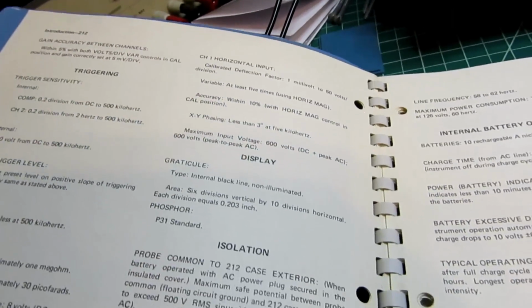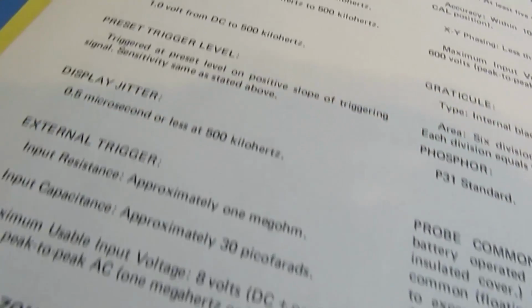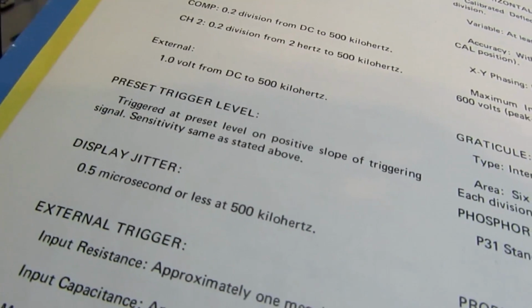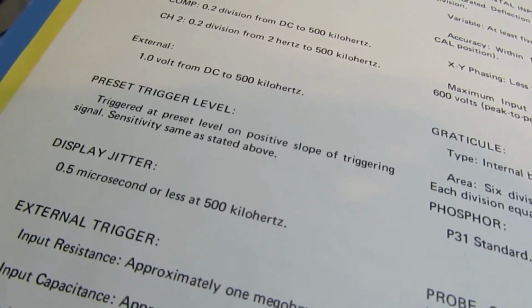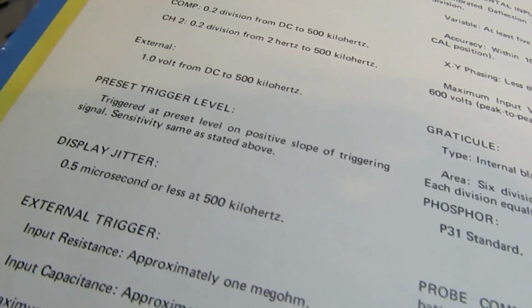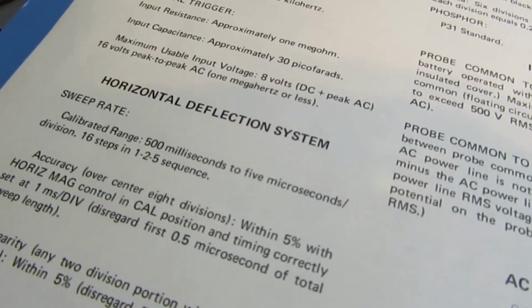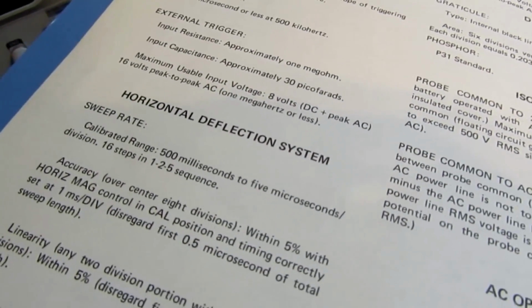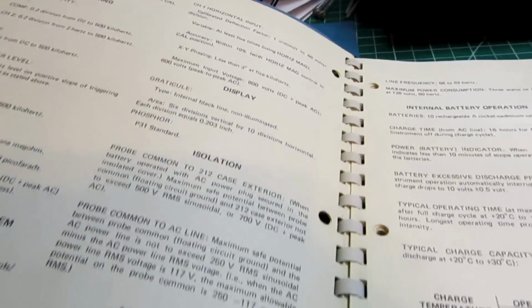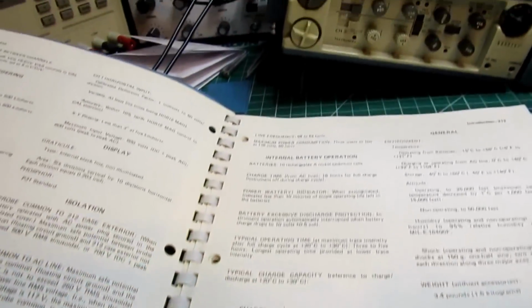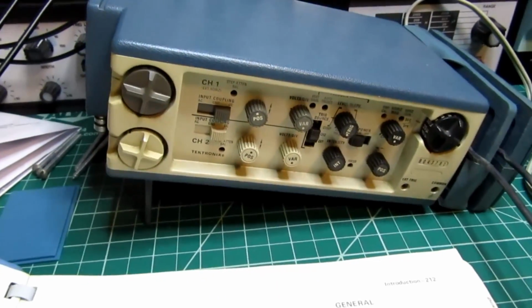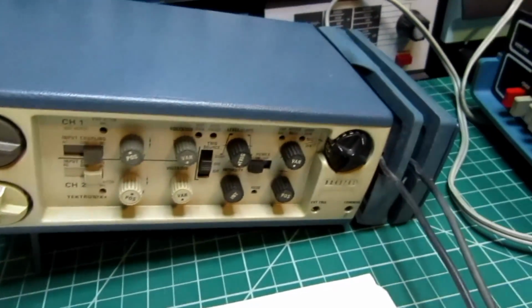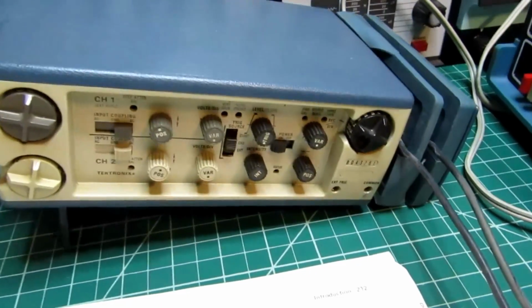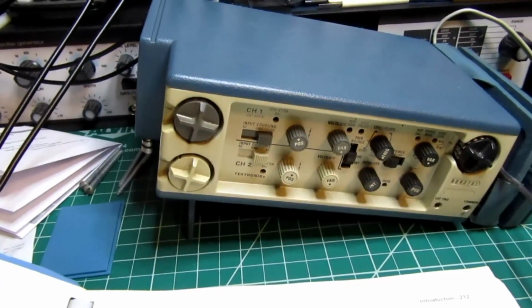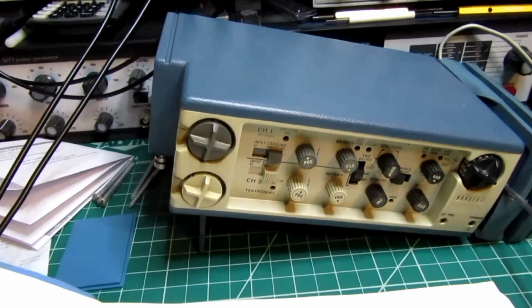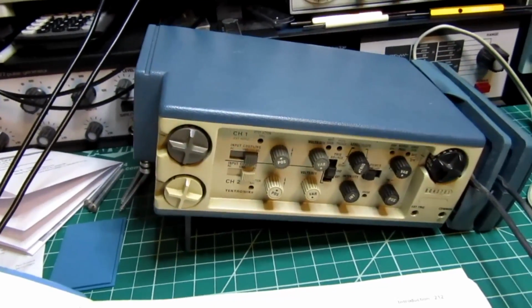Let's see. Yeah, as it says there, the preset trigger level is triggered at a preset level on a positive slope of the triggering signal, and it isn't specified exactly what that is. Anyway, let's see what we've got here. It is not isolated, so the power supply line cord of this scope is not electrically isolated from the probe, so you have to make sure if you hook it up to some equipment that you're hooking it up to something which is isolated.